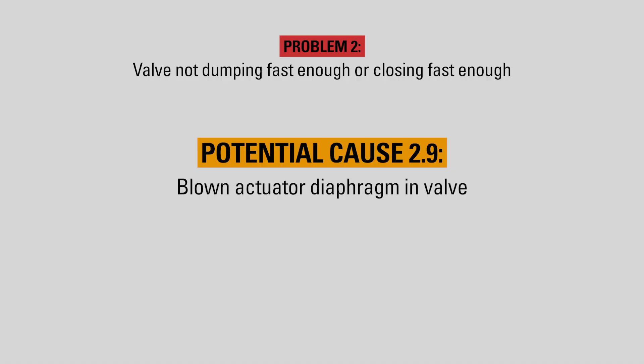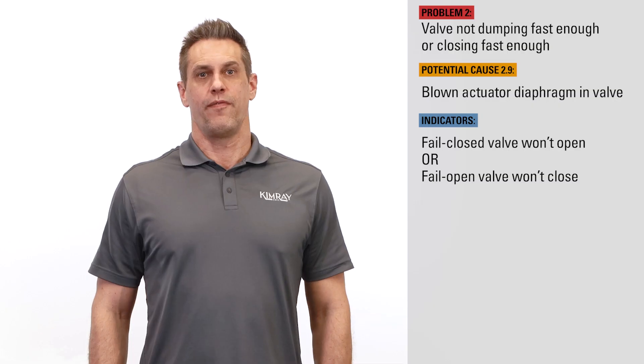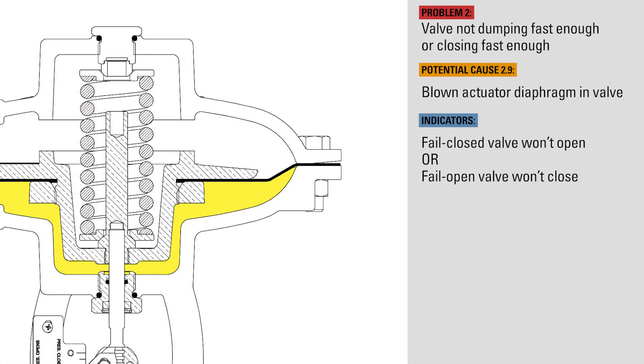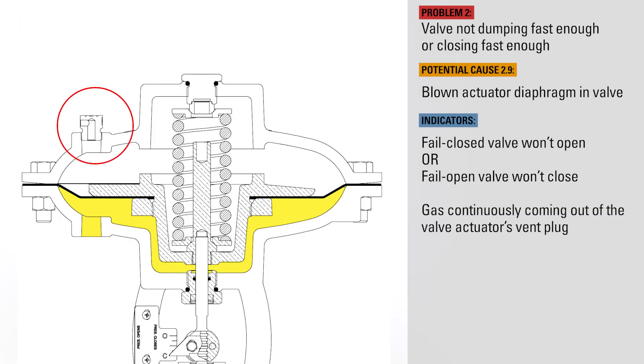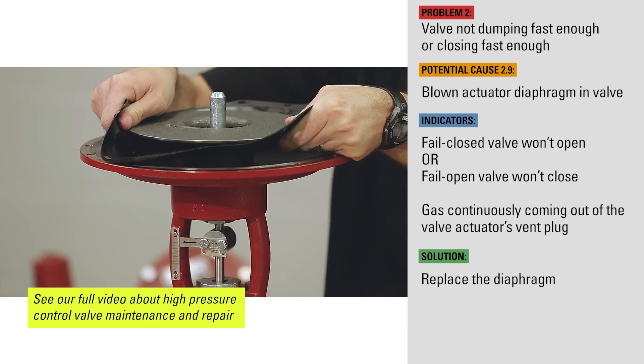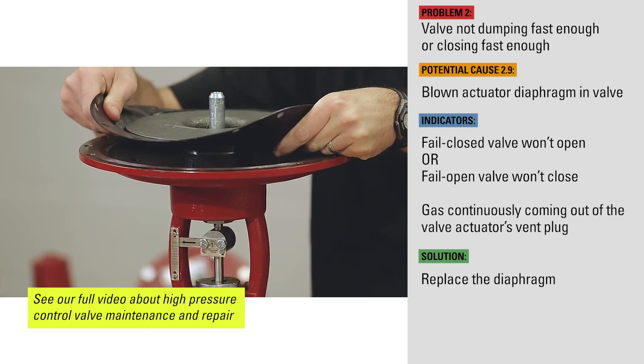If your fail closed valve won't open, or if your fail open valve won't close, it may have a ruptured actuator diaphragm, which is allowing the supply gas into both chambers of the actuator. The best indicator of this will be gas continuously coming out of the valve's actuator vent plug. To fix this, block and bleed the valve, then open the actuator and replace the diaphragm.